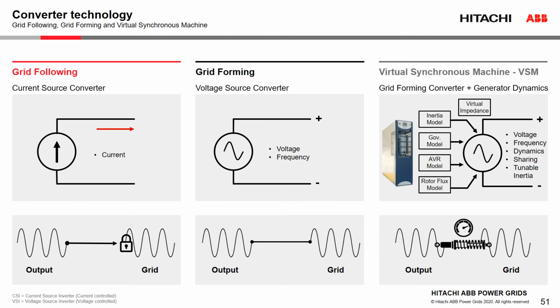When we move to the middle converter, this is a grid-forming converter or voltage source converter. These converters provide a voltage and frequency and have typically been used in an off-grid context. They provide a voltage and frequency reference to establish an off-grid network and hence are called grid-forming converters. The challenge with grid-forming converters is that they do not operate well in parallel with other voltage sources, whether that's synchronous generation or the grid, and can have a very stiff response in these scenarios.